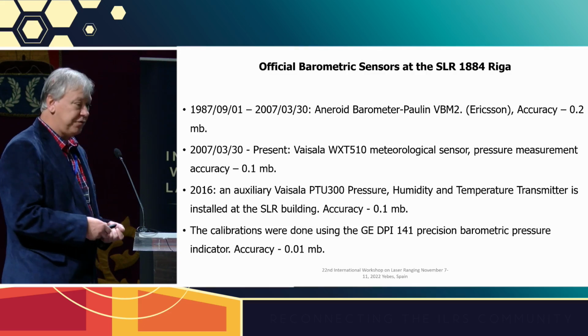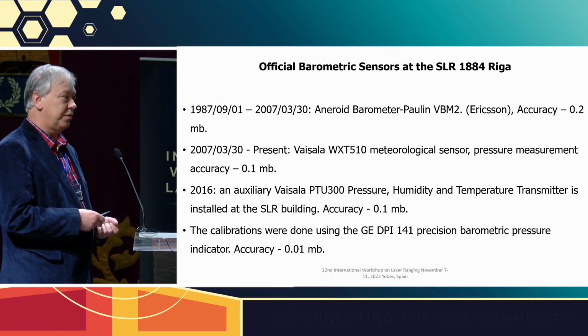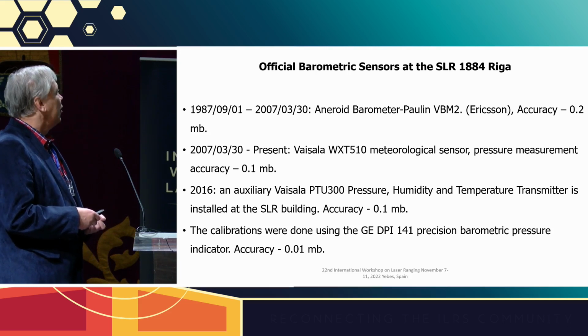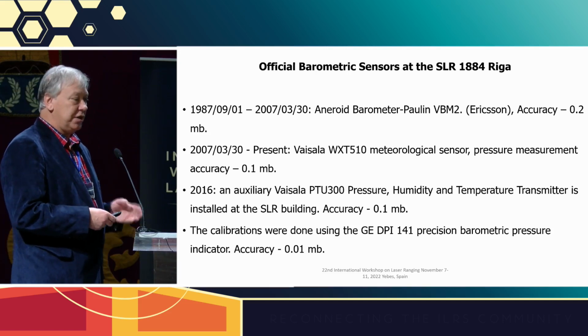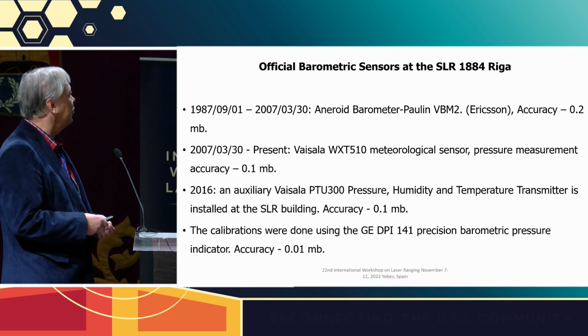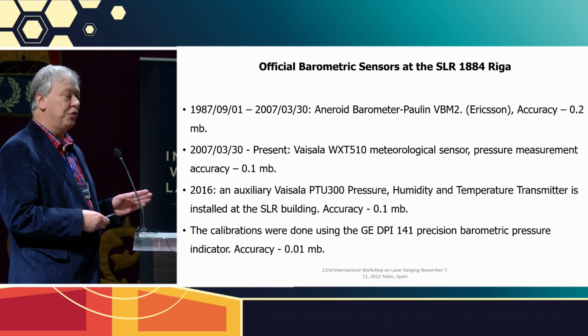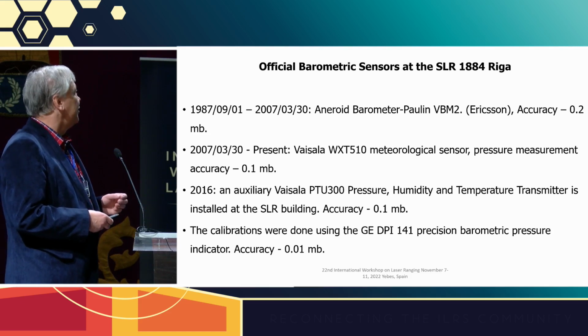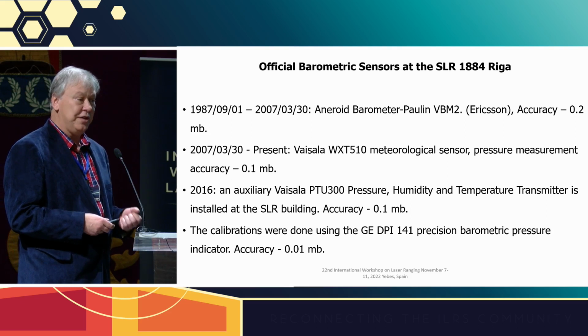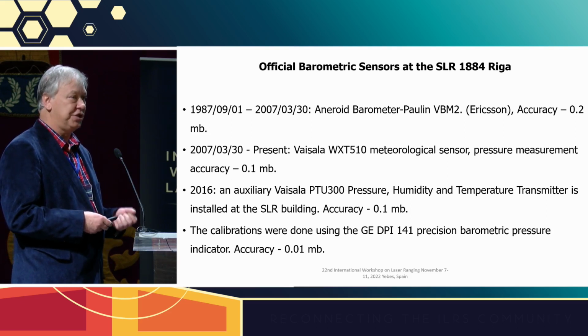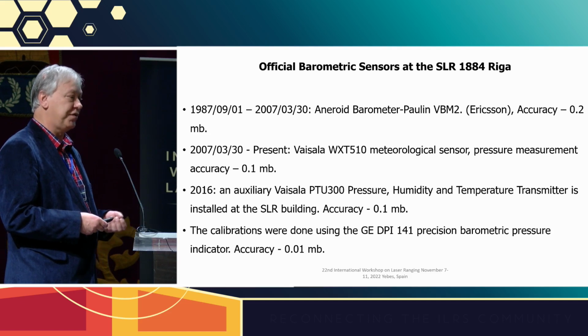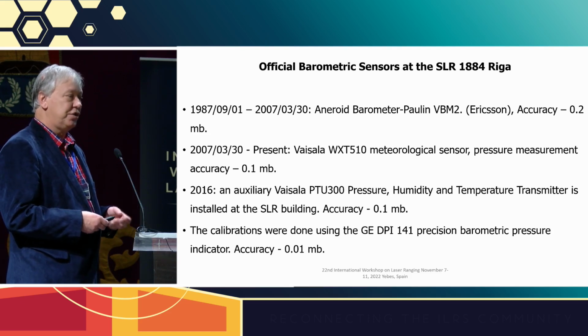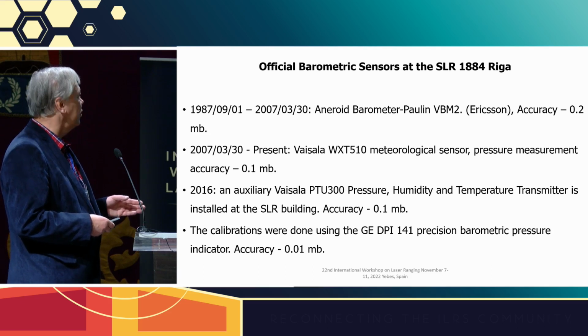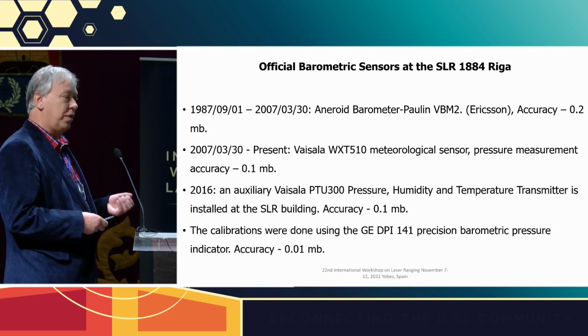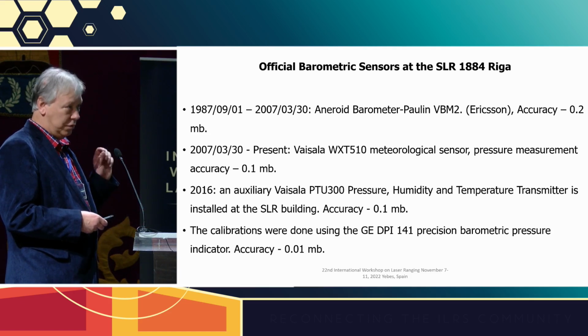First, a brief history of what we have used since the station started operating in 1987. For a very large period we used the aneroid from Ericsson, with accuracy about 0.2 millibar or hectopascal. Since 2007, we have the Vaisala WXT meteorological outdoor system, which measures pressure, temperature, humidity, wind, precipitation and so on, with a reported accuracy about 0.1 millibar.